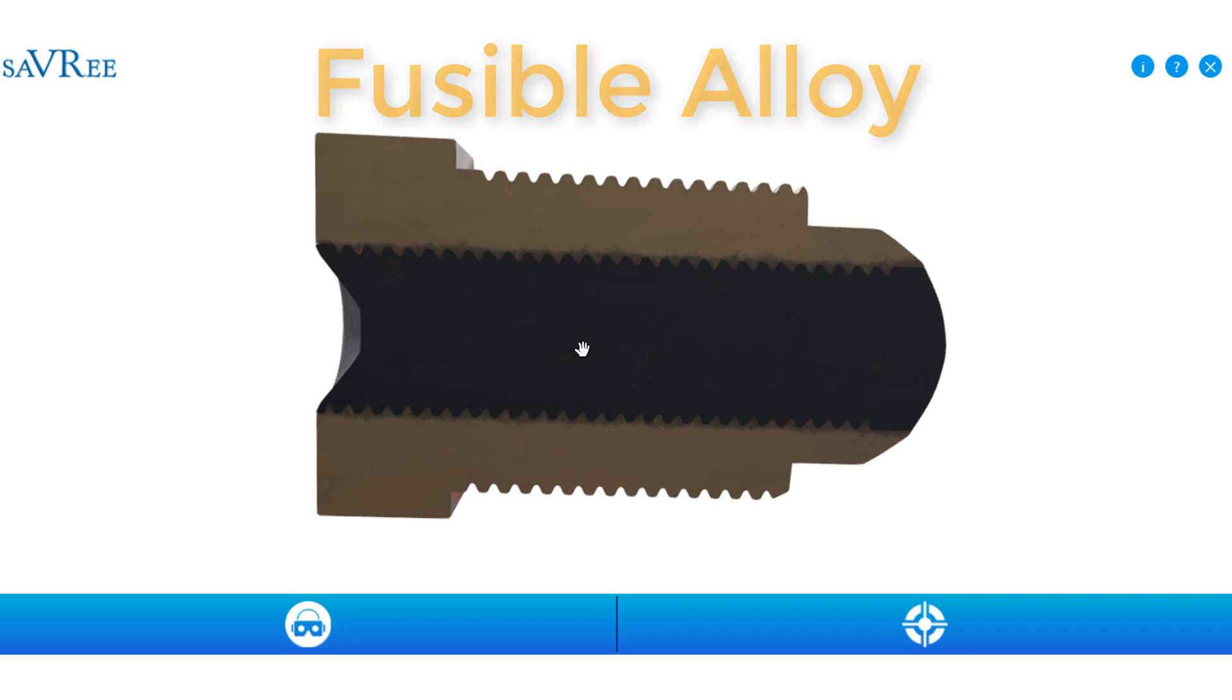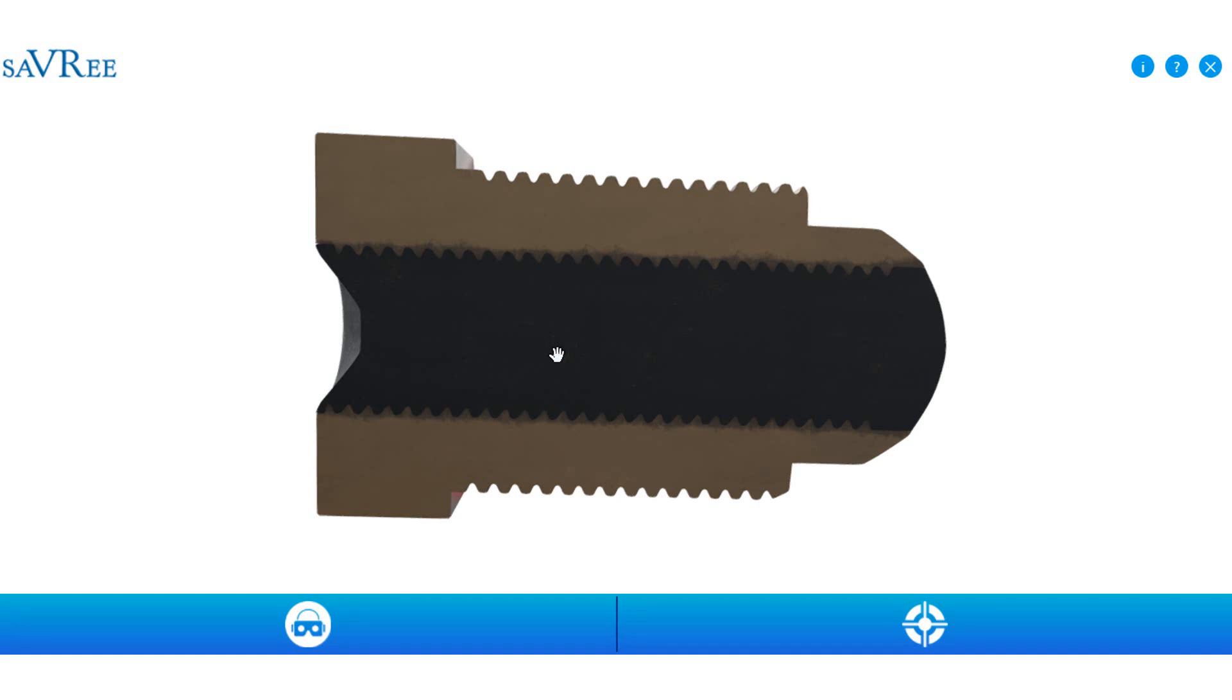That means if we expose the fusible plug to a high temperature, the black gray area will melt before the plug body itself. Now this is very important because this is the whole reason behind the fusible plug design.